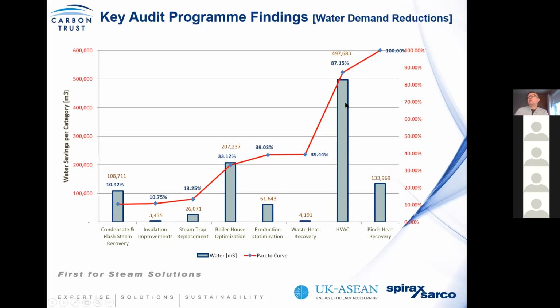The reason why HVAC is so high here is that you don't use water within HVAC, but what we have found is that you have refrigeration systems which reject heat energy through cooling towers. Cooling towers use water as a means of evaporation. Hence, especially in the Asia region, where there is a lot of need for humidification or dehumidification, water demand reductions could be quite significant.